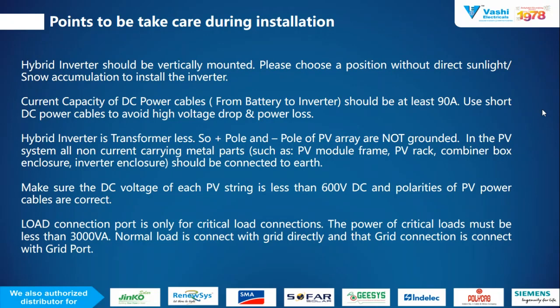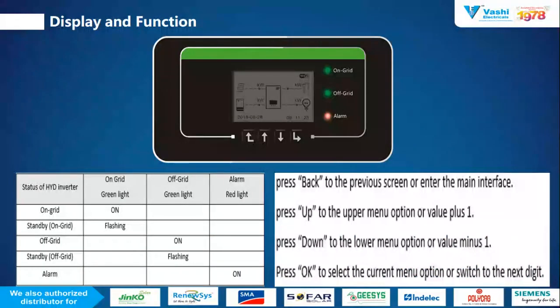Now, the inverter has a 4-inch super large LCD display. The display has 4 push buttons, like up and down for going upward and downward in the menu, and other than this, an OK button. First, on the left side, there is an escape key, which is an upward arrow. Means you can come out or back out from any other menu. So it will function as an escape key.